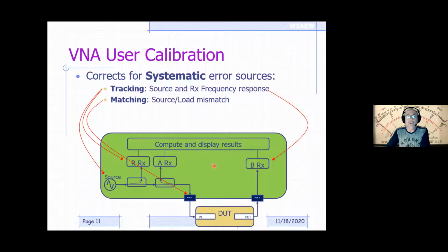Another systematic error source is the source and load mismatch errors. At the ports themselves, that can actually be accounted for in case the impedance at these ports isn't a perfect impedance match to your DUT or to the 50 ohm coax, for example. So that can be measured and removed.